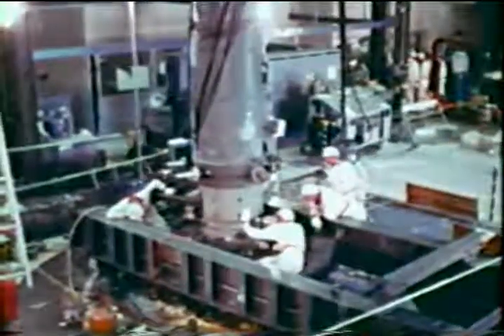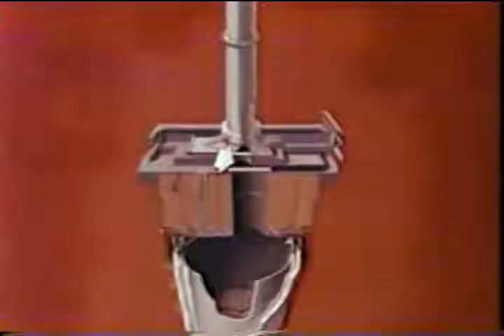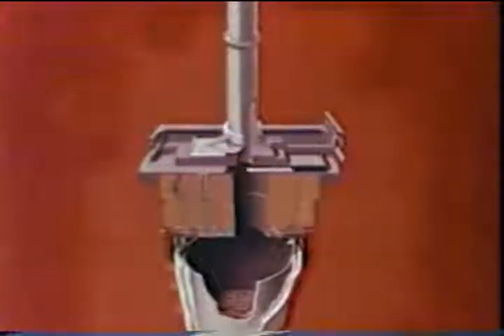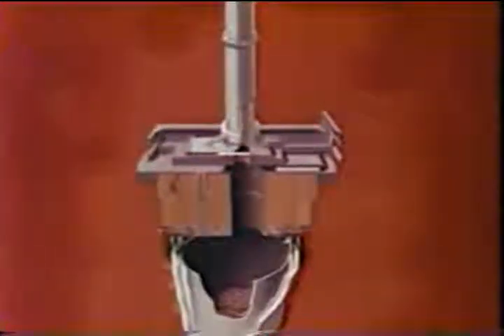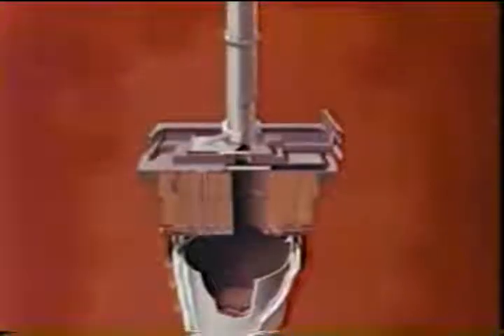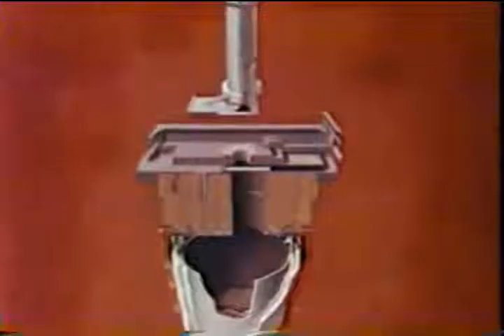The cask, with a new can inside, was moved to the reactor face. Following positioning of the moderator cask on the support bridge, the cask gate and 40-inch valve were opened and the new moderator can lowered into position. After the grapple was returned inside the moderator cask, the cask gate and 40-inch valve were closed. Subsequently, the moderator cask was moved away.